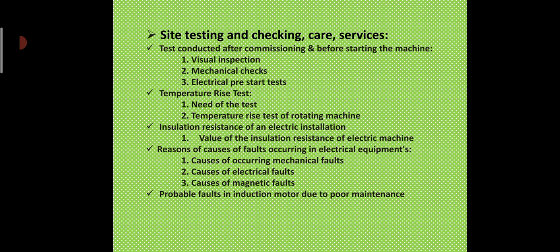Now, the need for the test. In the machine, a specific type of insulation is used. The insulation can bear temperature up to a certain limit. If the temperature developing in the machine is more than that, the winding may be damaged, and after some time it gets shorted and the machine may become useless. So it is necessary to know the rise in temperature in the machines.